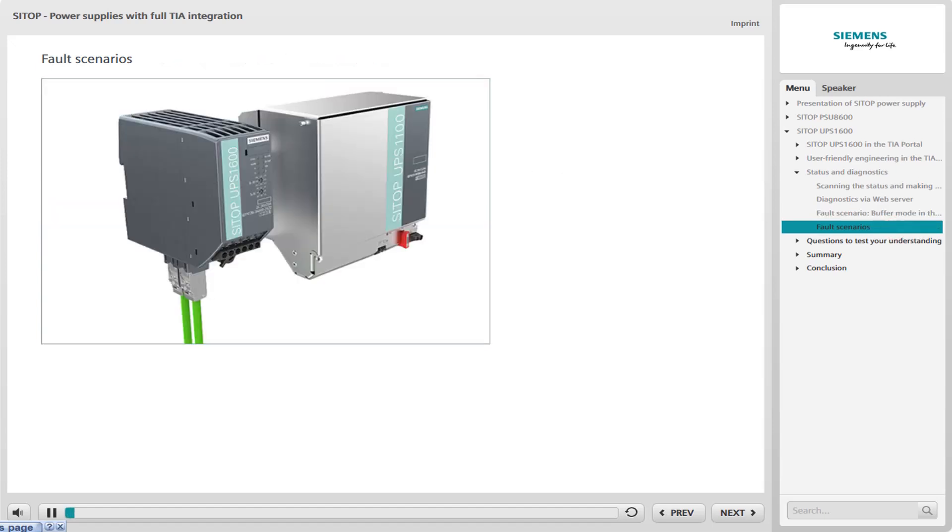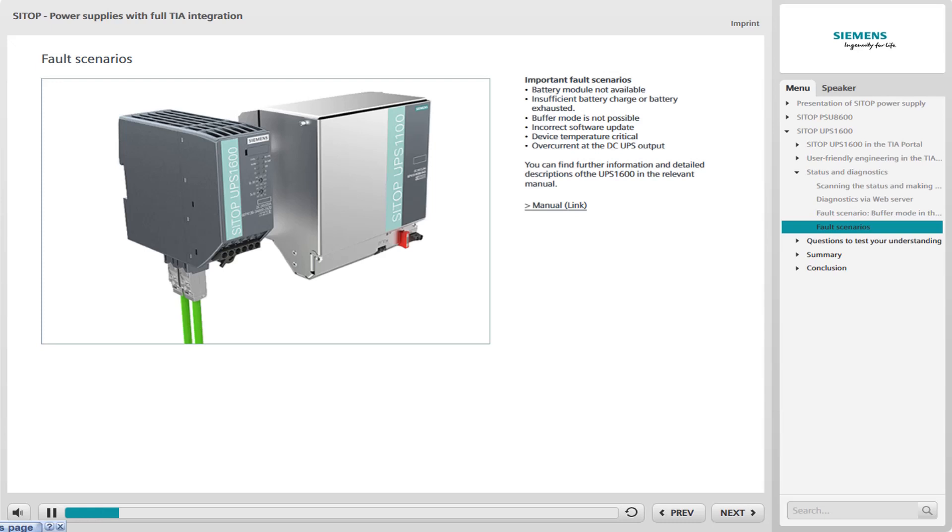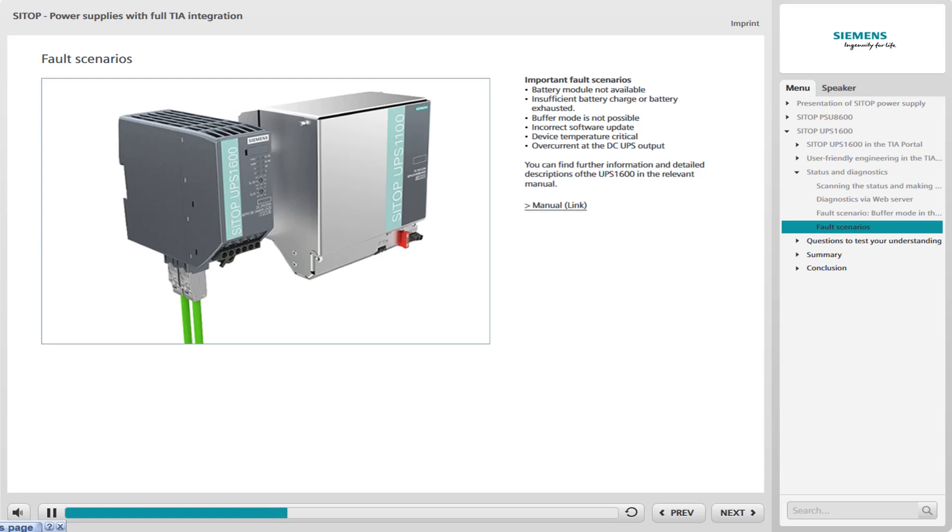Further fault scenarios that are reported and represented in a similar way are listed below. Battery module not available. This fault is reported if a battery is not available when an attempt is made to access it. Either the battery with the requested number is not connected, or communication with this battery has failed. Insufficient battery charge or battery exhausted. The battery charge level is too low to ensure the configured buffer capacity. Buffer mode is not possible. If this message is received, the settings, wiring and fuse must be checked.